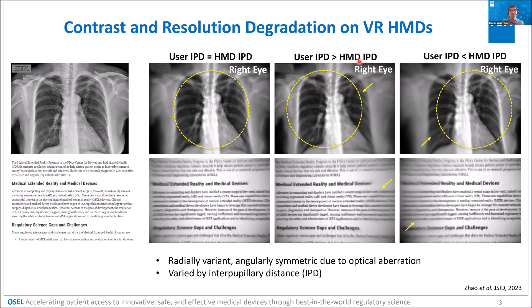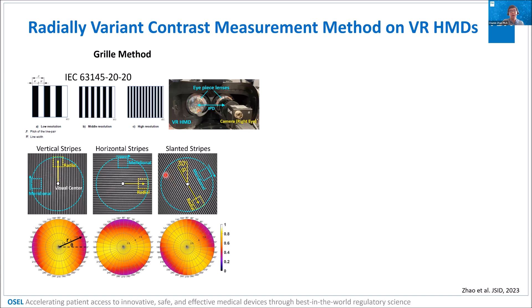To measure the contrast and effective resolution on MXR devices, the conventional method is using the grille method as documented in this IEC standard. You can load different grille test patterns with different spatial frequencies on the headset, and you can measure it at different locations across the display field of view. One limitation of this method is that because of the optical lens on VR headsets, that can cause a blur, especially in the radial direction. Depending on the orientation of the grille pattern, you can see, the bottom row is a contrast map. So you can see we got inconsistent results following the orientation of the grille patterns, which is not good.